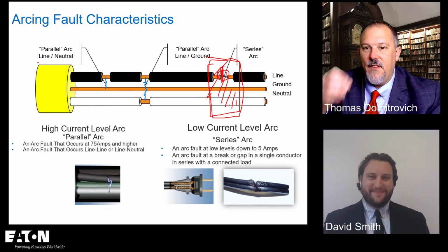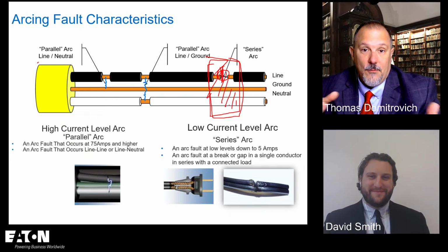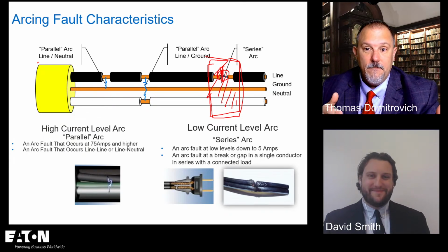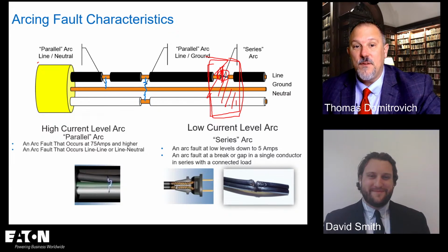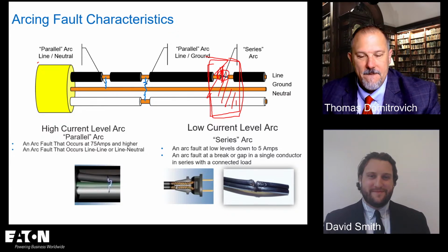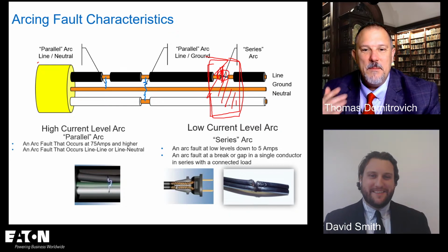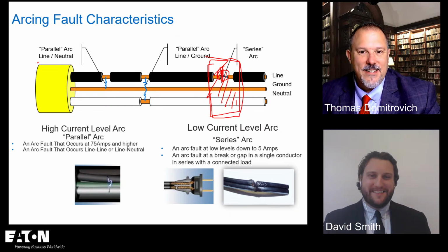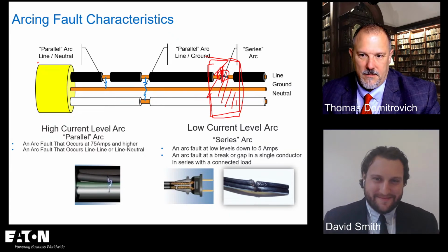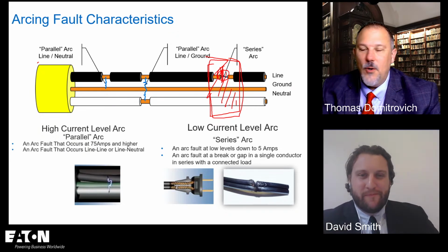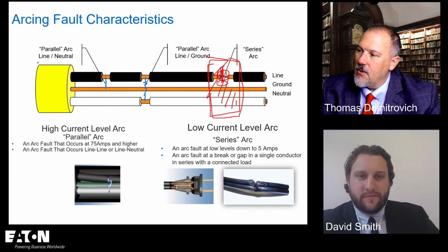And if that 5 amps trips, well, I have to detect, not if, it has to trip, right? And do you know how the branch feeder would detect that arc? How? What's in the middle of this, between those hot conductor and the neutral? A bare copper conductor. Gotcha. And so what would happen when I do this series arc, I would basically burn away the paper that's in between here. And I would create enough carbon that it would go right back over the equipment grounding conductor.